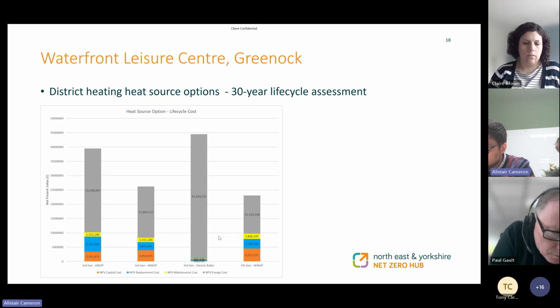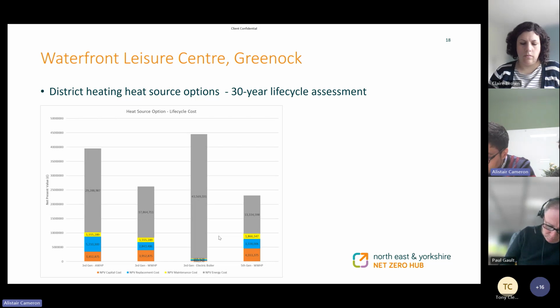And then number 1 in terms of performance was the 5th generation heat pump. So that's your low grade heat circulating to each building, then locally upgraded at each building. So that was number 1 in terms of performance. And that's largely because the energy cost, that operational running cost, that grey bar goes from 17 to 13. So you're taking advantage of that increased efficiency of that 5th generation technology.